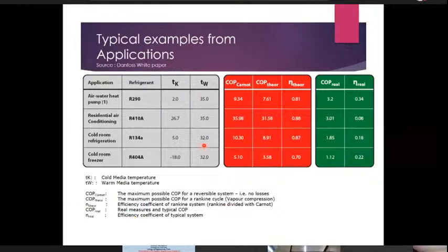Residential air conditioning using R410a. The ideal COP can be 36 and the theoretical can be 31.58, and real systems are around 3.5. Today we can see systems with 3.7 also, but there is a huge gap between the 3.7 and the 31, and this is opportunity for engineers. What are the newer technologies that we can deploy to get this number closer to the theoretical number? We will never get to 31.58 because we will always have some irreversibilities, but how closely can we approach this?